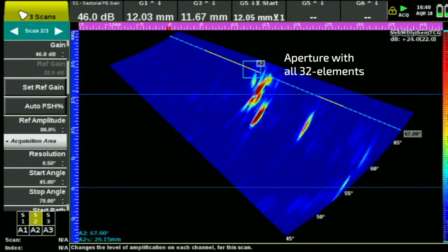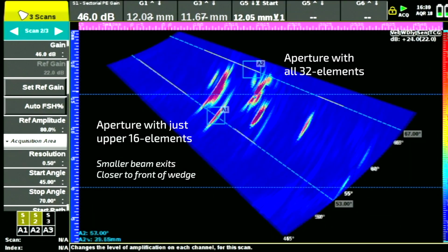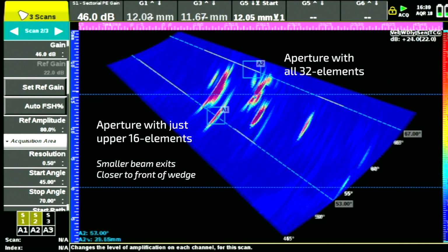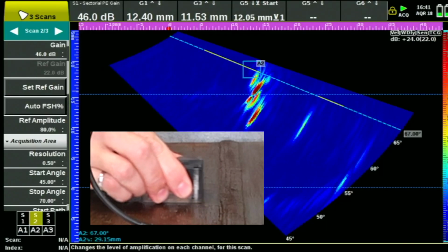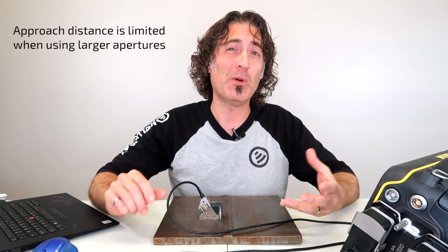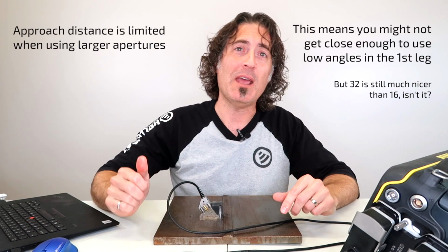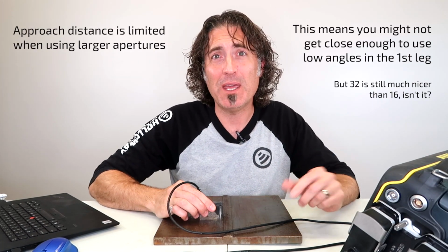Now let's switch to the 5 megahertz 32 element aperture. The first thing that you notice is that the entire signature for the crack is pushed over further on the S-scan. And this is the downside of using larger probes with big apertures. The center of the beam comes out from the center of the aperture. We're using all 32 elements, so compared to the 16 element aperture, which I did put more towards the top of the probe, this one comes out more towards the backside, which means that I just don't have the approach distance that I want. You will get better height sizing, like we mentioned before, the closer you get and the steeper the angle you get. In this case, I can't really do that, so we get what we get.